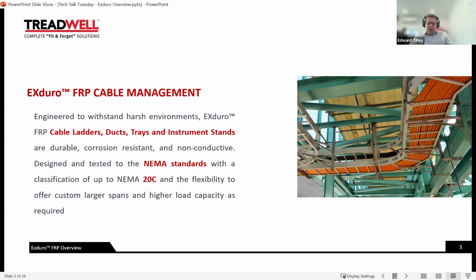Second thing is dissimilar metals. Where we've got a mild steel structure and we want to use a stainless cable ladder for durability, we need to somewhere isolate to prevent galvanic corrosion and dissimilar metals problems. So that's number two. And number three is weight. FRP cable ladder is a lot lighter than your traditional metallic product. It's a lot easier and faster to put in, because you're reducing your labour requirements, no hot work on site, that sort of thing, but more on that in due course.